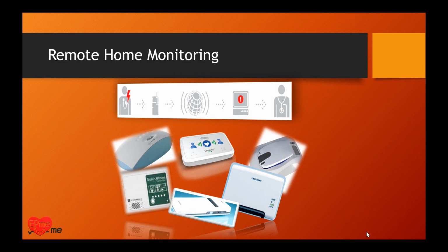It has periodic telemetric transmissions, traditionally using the cellular, the mobile telephone network, to a central server or in the cloud of the manufacturer of the company. Now, that patient's data goes into a certain area which the medical team can assess by accessing it through their dedicated website, and they can actually do a follow-up visit for these patients.